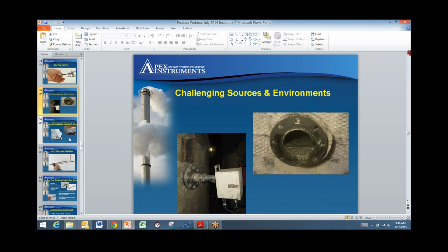I would think if we had issues with leakage, you wouldn't be able to send somebody in there to maintain it, so. Correct. Yeah, we had that at one point, where a brick or something fell down and damaged the duct, and it leaked into the annular space. Okay. I've got a site that I was at back in January. They actually have to pressurize the annulus from down at the bottom just because the stack leaks so bad. They keep it pressurized all the time just so the guys can get up there and work. And it's one of those sites you have to carry gas masks with you all the time, just in case the fans go off. So it's not the best environment, but we've been in that site 6 months or more now. Okay.